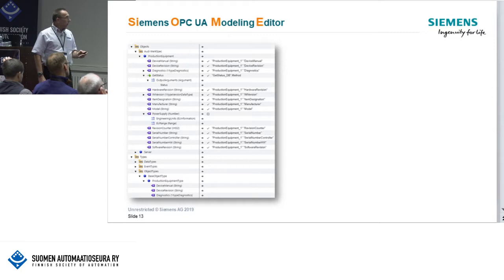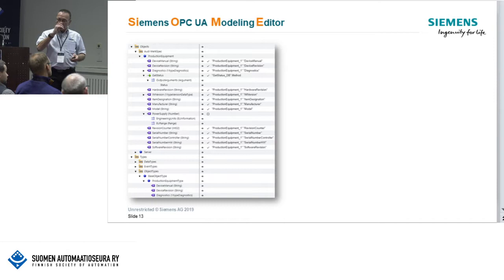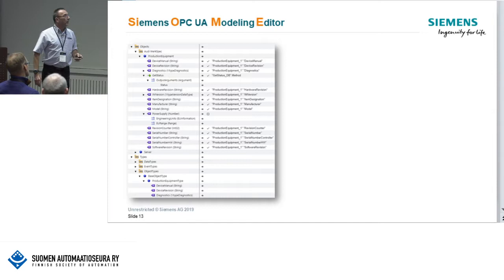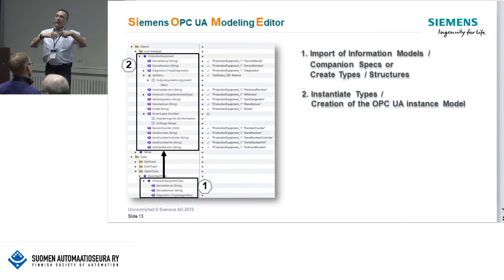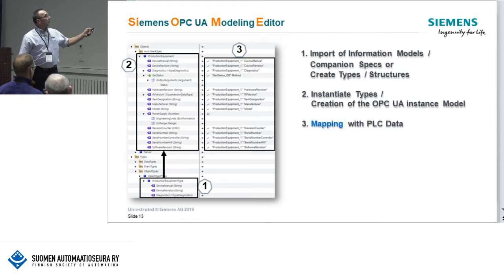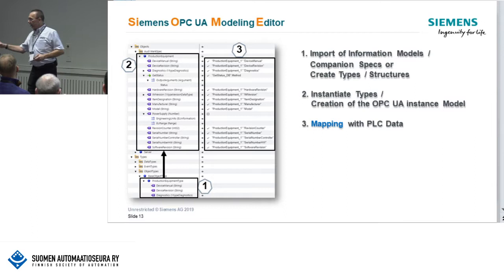In a nutshell: the first step is import of information models and companion specifications. The second step is to instantiate types — you create from the type the real instance, or several instances of that type. After that you create the mapping of those instances. Then you download it, transferring it directly to the PLC.